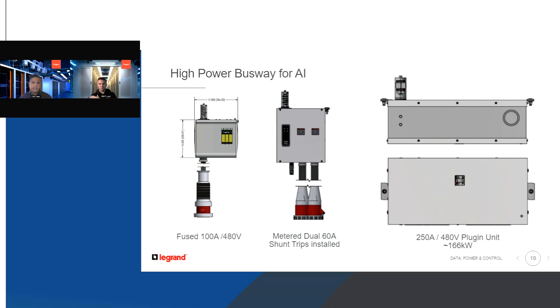The middle one is interesting—it's a metered dual 60 with shunt trips installed. We got requested to do this because of the shift from air to more liquid cooling in the data center. The request is driven by giving a user the ability to remotely shut down the breakers if something were to go wrong with the liquid cooling. This is a modification we've been fielding requests on, and we're starting to deploy plugins with these shunts to give customers that ability, providing an extra level of security if they use liquid cooling.